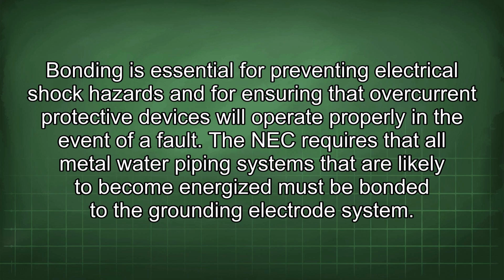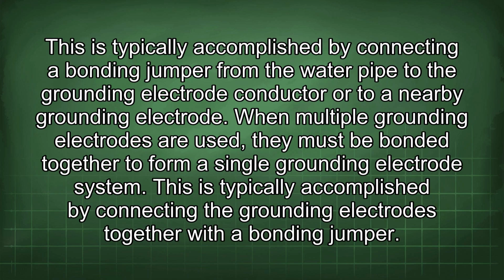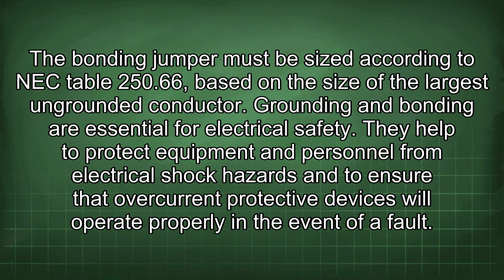The NEC requires that all metal water piping systems that are likely to become energized must be bonded to the grounding electrode system. This is typically accomplished by connecting a bonding jumper from the water pipe to the grounding electrode conductor or to a nearby grounding electrode. When multiple grounding electrodes are used, they must be bonded together to form a single grounding electrode system. This is typically accomplished by connecting the grounding electrodes together with a bonding jumper. The bonding jumper must be sized according to NEC Table 250.66, based on the size of the largest ungrounded conductor.